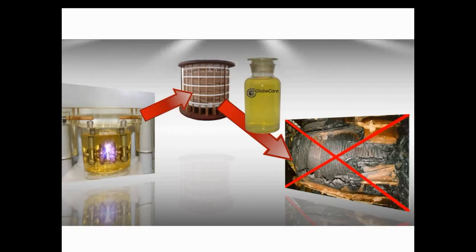And here we have come to the next core point. How does the paper insulation lose its strength? It happens because of oxidization, which takes place in a transformer. Besides, all the metal and paper are not sitting alone inside it, as the transformer is filled with mineral oil. Thus now we have arrived at the application of regeneration technology.